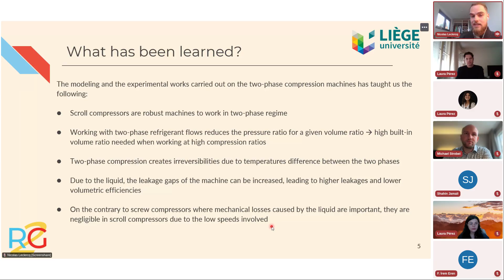On the contrary, in screw compressors, mechanical losses caused by the liquid are important, because at the extremity of a screw you can have speeds up to 50 or even 100 meters per second, so you have huge mechanical losses. Here, they are negligible in scroll compressors, so even if you have liquid, it's not going to increase the compression work. And so that was it from my side, and I hope we can have an interesting discussion after our last presentation.